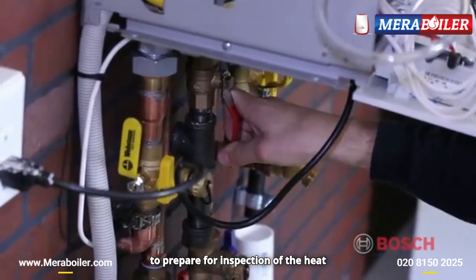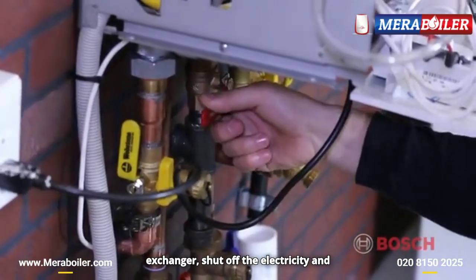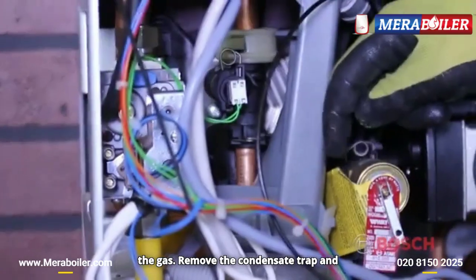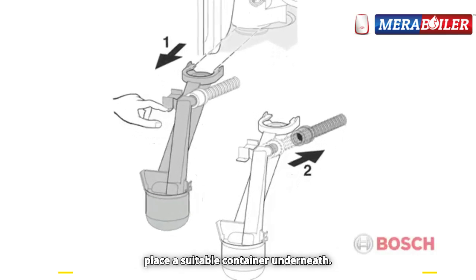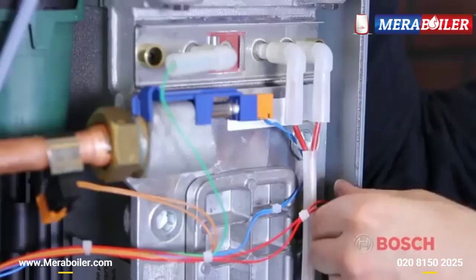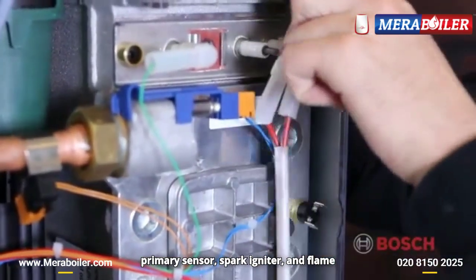In order to prepare for inspection of the heat exchanger, shut off the electricity and the gas. Remove the condensate trap and place a suitable container underneath. Remove the wires from the high limit, primary sensor, spark igniter, and flame sensor.